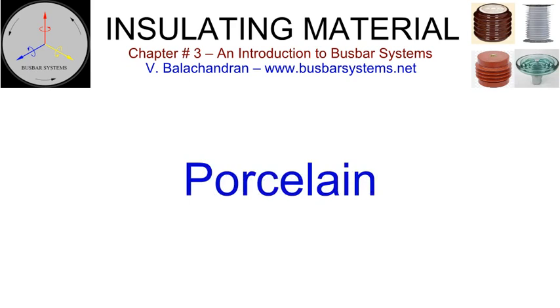Porcelain. Porcelain insulators and bushings have been used in the electrical industry since its inception. They have excellent dielectric properties, long life, are resistant to atmospheric corrosion and ultraviolet radiation. The infrastructure cost to manufacture porcelain component is very heavy. The process is extremely labor-intensive and requires very skilled engineering and operating staff. The dielectric properties of a porcelain insulator, in most cases, can be fully restored, after a flashover across its surface, by washing with solvent and water and cleaning the same.